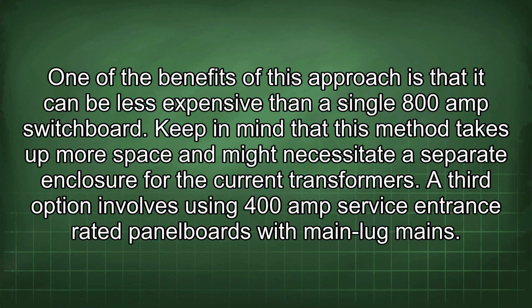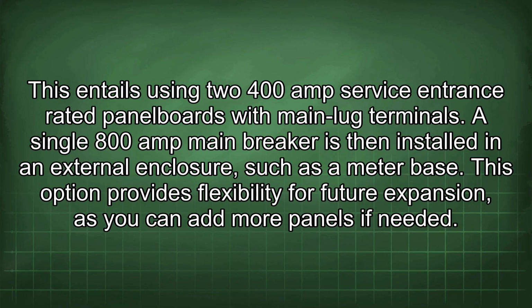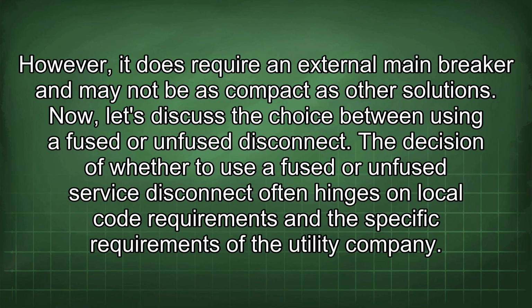A third option involves using 400 amp service entrance rated panelboards with main lug mains. This entails using two 400 amp service entrance rated panelboards with main lug terminals. A single 800 amp main breaker is then installed in an external enclosure, such as a meter base. This option provides flexibility for future expansion, as you can add more panels if needed. However, it does require an external main breaker and may not be as compact as other solutions.